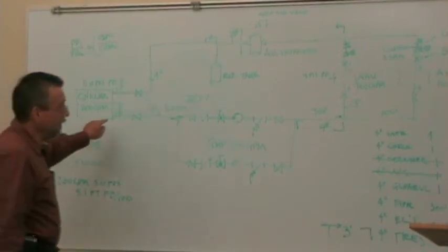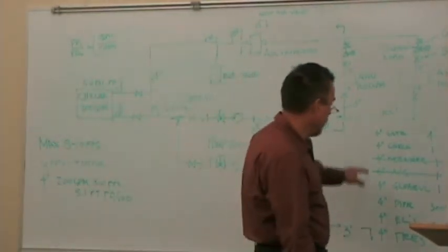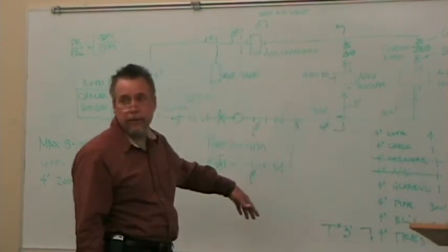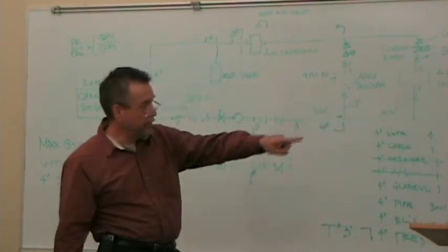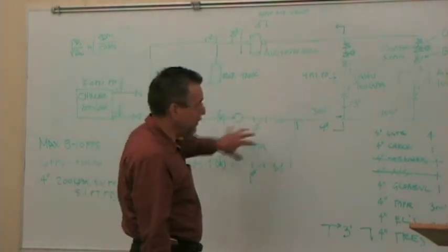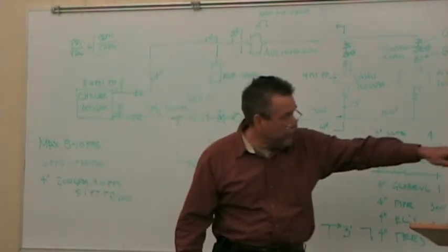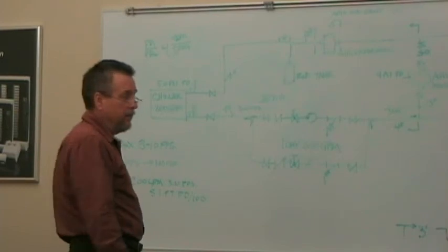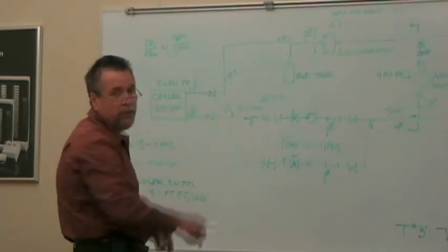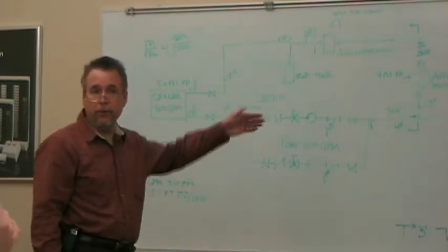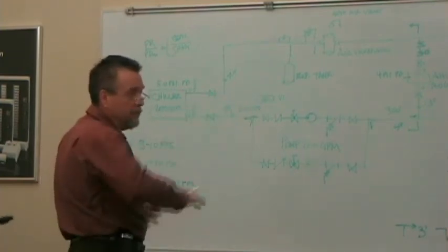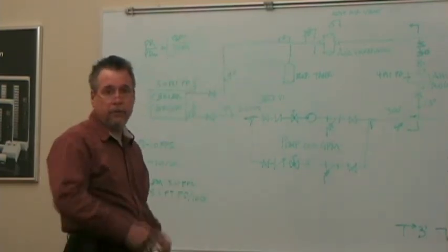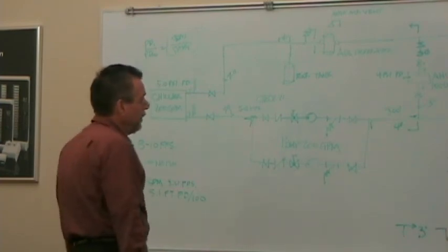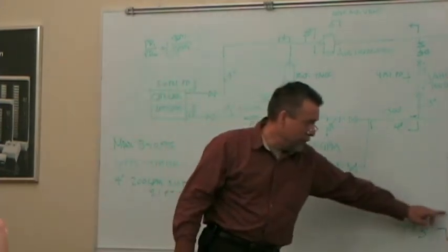So you can see, the point I'm making is piping, yes, is critical, but if we take all the components out, piping was about 50% of my pressure loss for the entire system. And this is pretty standard. These rules of thumb hold unless I've got a huge building or a campus where I'm running thousands of feet of pipe. So you can see elbows.